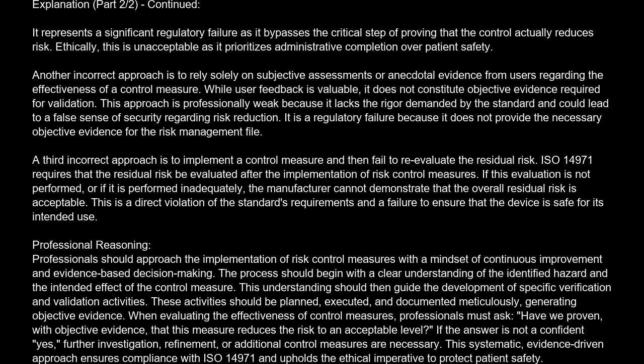Professional reasoning. Professionals should approach the implementation of risk control measures with a mindset of continuous improvement and evidence-based decision-making. The process should begin with a clear understanding of the identified hazard and the intended effect of the control measure. This understanding should then guide the development of specific verification and validation activities. These activities should be planned, executed, and documented meticulously, generating objective evidence. When evaluating the effectiveness of control measures, professionals must ask, have we proven with objective evidence that this measure reduces the risk to an acceptable level? If the answer is not a confident yes, further investigation, refinement, or additional control measures are necessary. This systematic, evidence-driven approach ensures compliance with ISO 14971 and upholds the ethical imperative to protect patient safety.